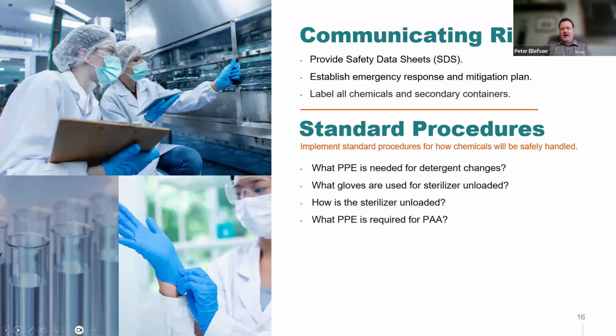Something that we always recommend is, when you're unloading these sterilizers, for example with hydrogen peroxide, something we see all the time is people opening the sterilizer and not taking a step back. It's very easy to just take that extra moment, open the sterilizer, and if there's a monitor in place above that sterilizer, take a step back, see exactly what the exposure level is going to be, make sure that it's deemed safe, and then continue with what you need to get done. It's an extra few seconds, but in the event that a lot of hydrogen peroxide comes out of that sterilizer, it can really save the employee in the long run.